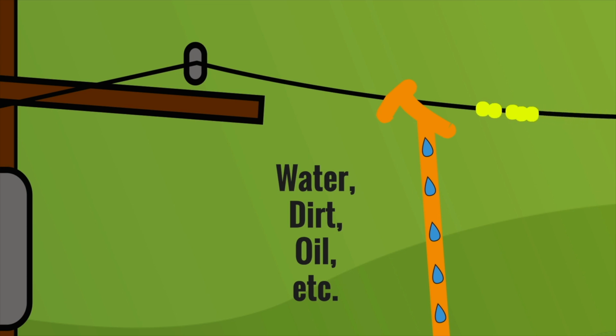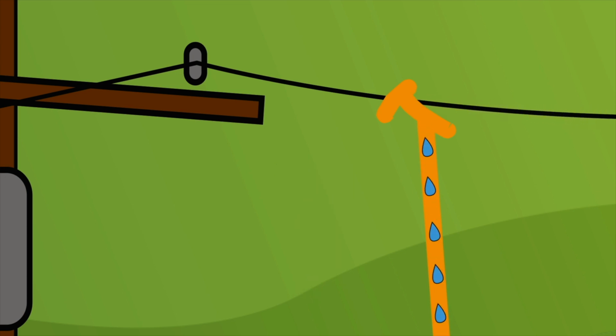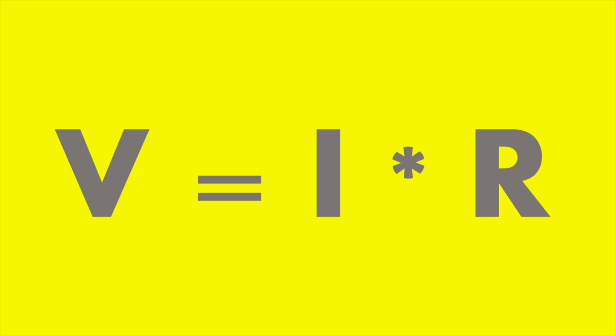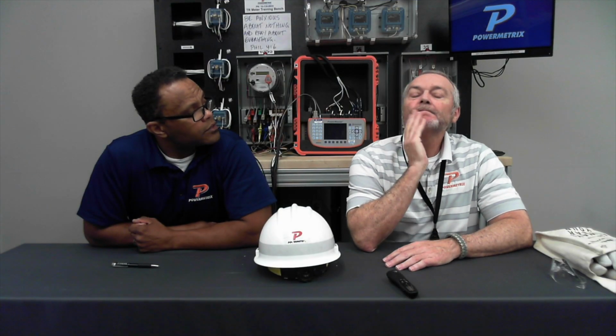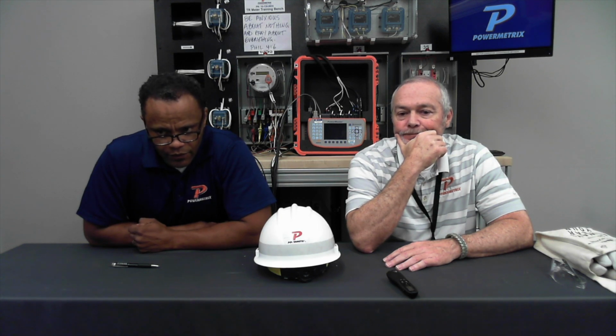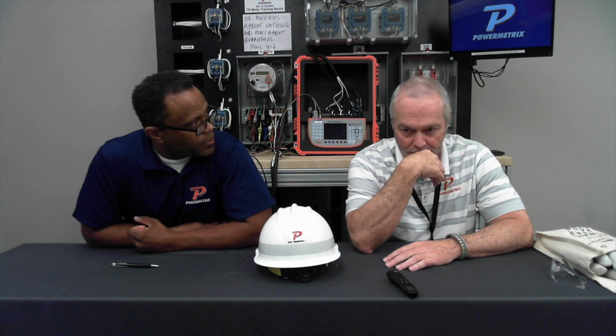Ray, sometimes we have questions from customers asking how they take care of their high voltage sensor link probe. What's your recommendation? On that probe, what I normally do is, the manual says you can use denatured alcohol to clean the fork really good, because when you start taking it up there near the conductor it starts to turn black, you've seen it, and dirt collects. You can also take compressed air, and right where the DB9 connector joins the receiver part, you can actually remove those two screws and blow compressed air in there and clean that DB9 connector out. So there's a lot of things to do.